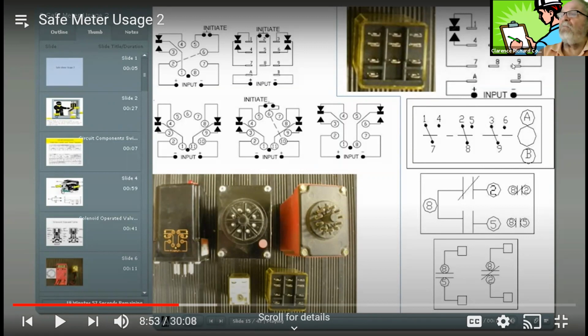These are your triple pole double throws. This is the same thing as what we have here. They just didn't decide to show it there because it was too hard to see by adding those, but this here is going to mimic that. So if you go from your C contact on the one big relay that we're looking at, that went from C to NO and NC. You take from 7 to 1. 1 is your NC contact. 4 is your NO contact. This is your armature right here. When you energize this, this is going to toggle from 1 to 4.